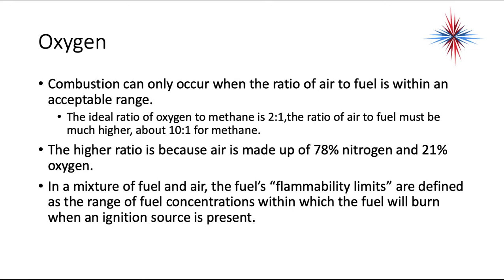Combustion can only occur when the ratio of air to fuel is within an acceptable range. The ideal ratio of oxygen to methane is 2 to 1. The ratio of air to fuel must be much higher — about 10 to 1 for methane — because air is made up of 78% nitrogen and 21% oxygen. The fuel's flammability limits are the range of fuel concentrations within which the fuel will burn when an ignition source is present. You can have too much fuel or too little fuel, and it won't burn.